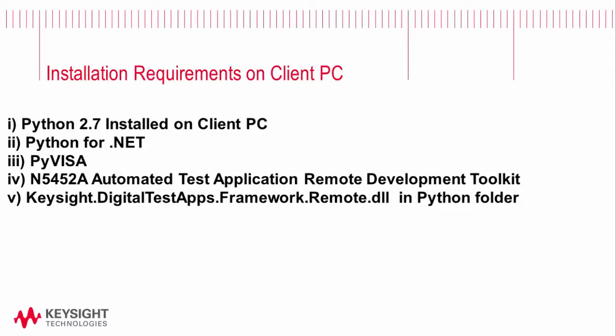The next step is to make sure PyVisa is installed. Now it's not strictly required to have PyVisa installed on the client PC, but it's helpful and is a requirement if at some point we want to send SCPI commands to the instrument.